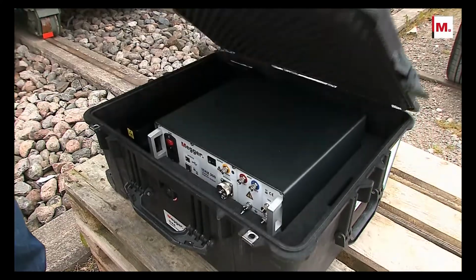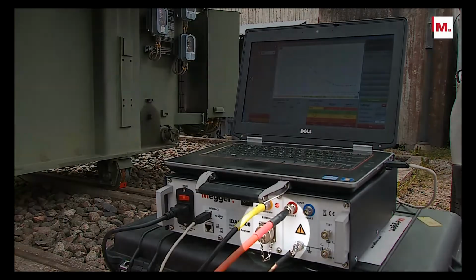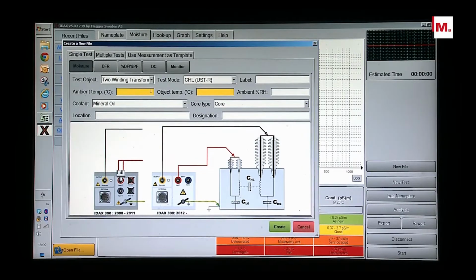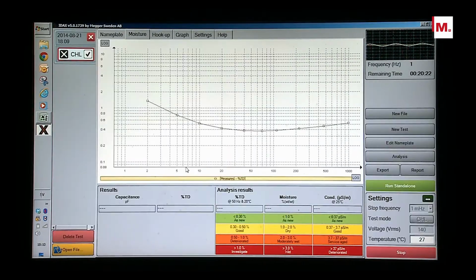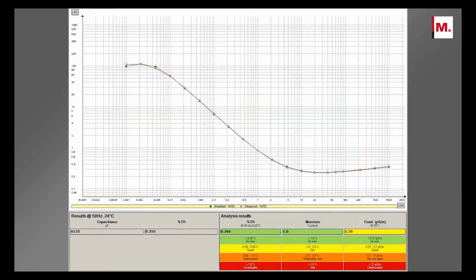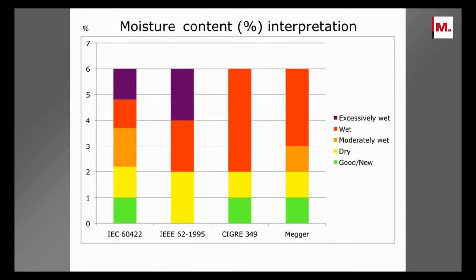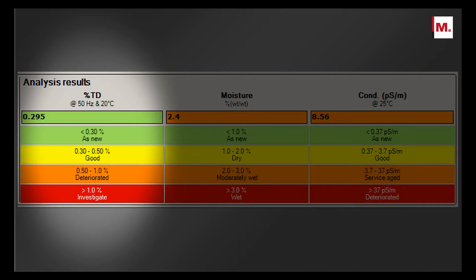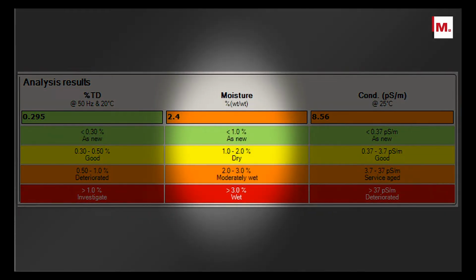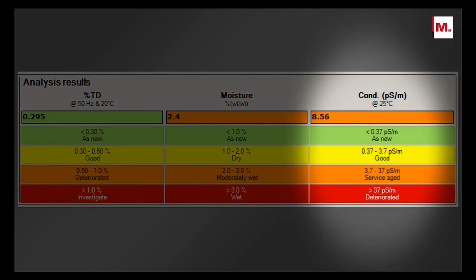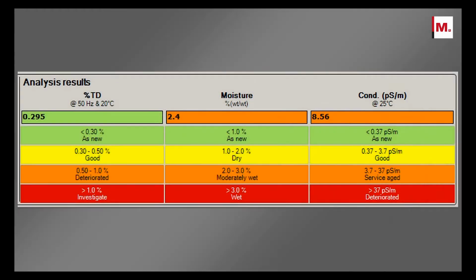The test is easy to carry out. Connect 3 cables. Enter the insulation temperature and start the test. When the test is finalized, the data is automatically analyzed and presented. Several international standards offer guidelines for insulation assessment in terms of power frequency tan delta, moisture content in the solid insulation, and conductivity of oil. Referring to these standards, IDAX provides the user with a thorough description of the insulation condition.